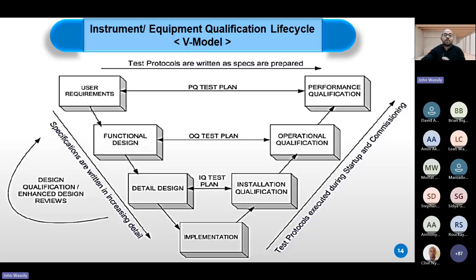Also, I want you to get familiar with another representation for the equipment qualification life cycle. It's usually presented in the regulatory guidelines by the V model. The V model here is presenting the same qualification phases and the same qualification testings that we've explored together in terms of user requirement specification, design specification, design qualification, installation qualification, operational qualification, and performance qualification. But here it's presented in a V model shape in order to build a correlation between each phase and how it's correlated to the previous phases. This is just for you to be familiar with how the equipment qualification life cycle could be presented in the regulatory guidelines.